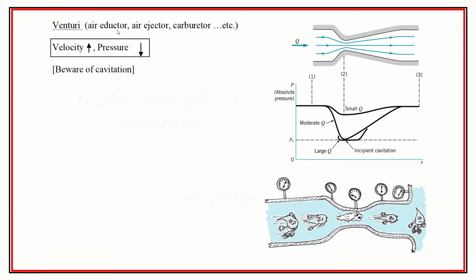Now, an air eductor can be a very useful thing where you have maybe compressed air, and you could put it into an air eductor and put the little hose or the little fitting that is attached right here, and you can suck up liquids with this. So you could use air as sort of a small pump, if you will, and it's a very effective way to maybe get the prime started on a centrifugal pump.